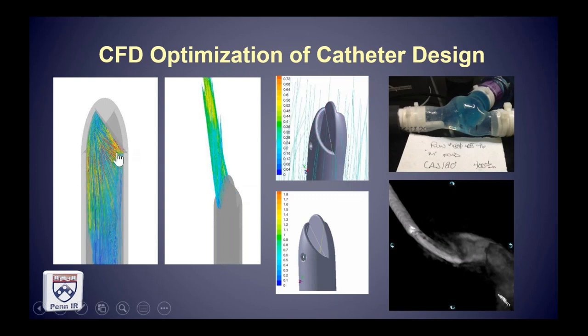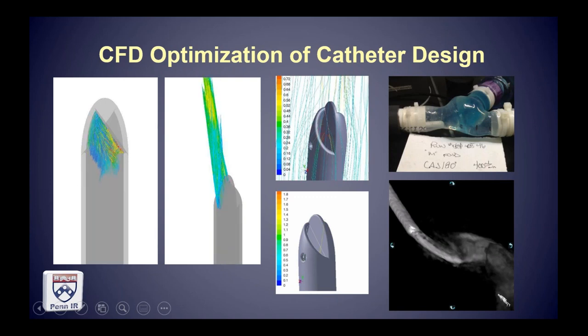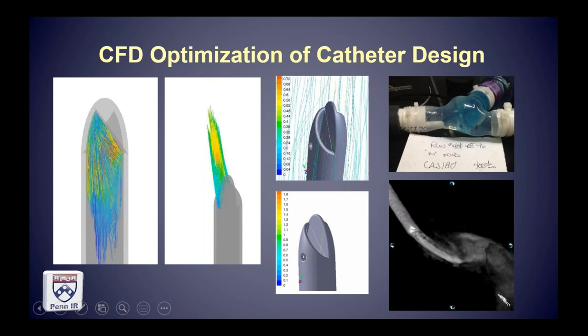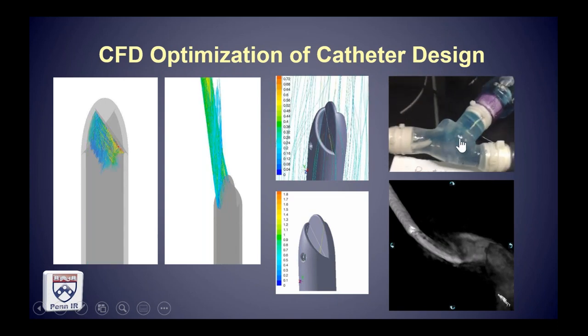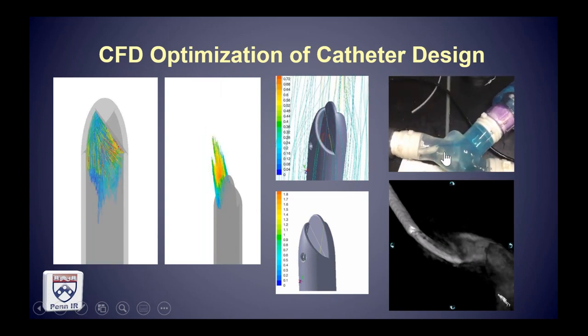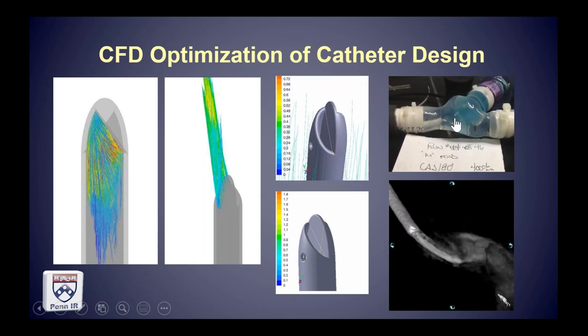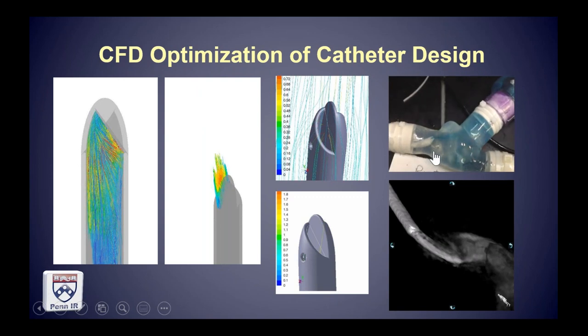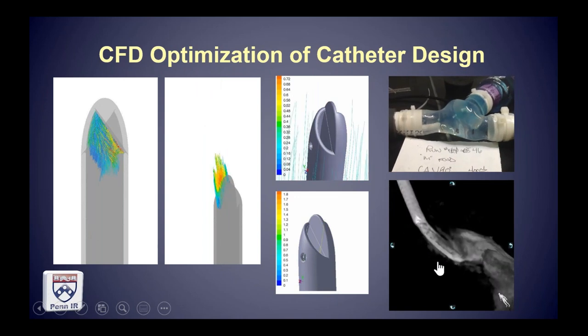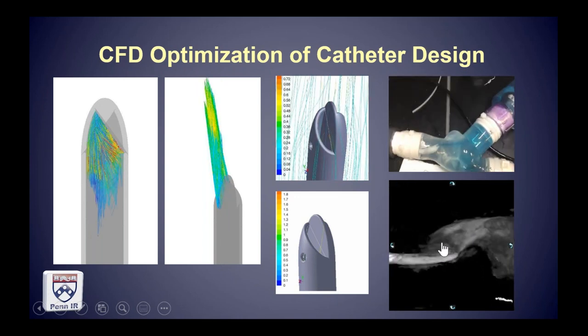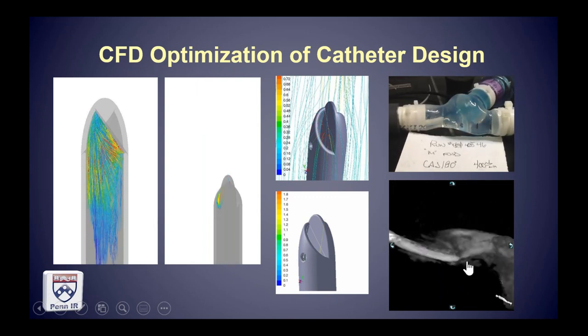You want a gradient of velocities and vectors as blood enters and leaves the catheter to minimize platelet activation, platelet adherence, thrombosis, and biofilm formation. Ultimately you test that in a bench model of a right atrium, which is where the tip of the dialysis catheter is typically placed. One experiment showed flow being deflected by the prototype catheter away from the long lumen toward the right ventricular outflow, and an animal model with three-dimensional CTA confirmed the same phenomenon occurring.